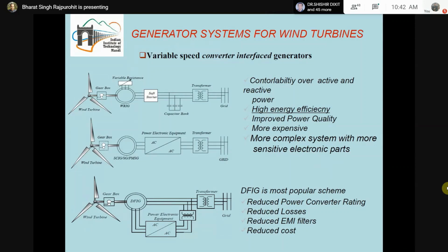So this scheme is there. The variable speed operation generally requires about 30% with reference to the base speed. So that's why the rating of this power electronic component is only 30% of the stator rating. It means the rating of this power electronic component, as compared to the middle figure, is almost 1/3. So here we are able to see there is a huge saving in terms of component cost, because the rating of the power converter is just 1/3.